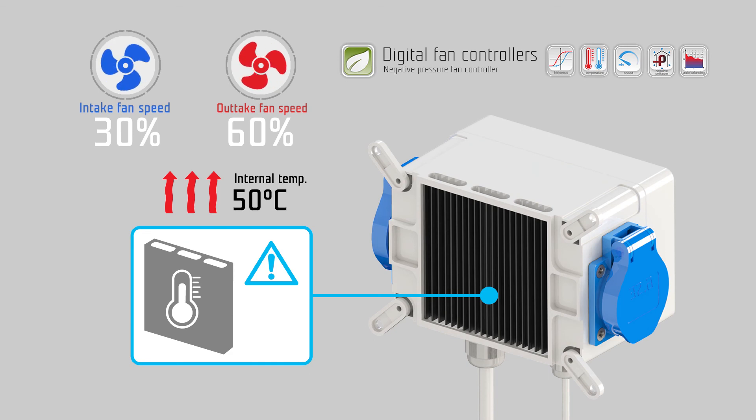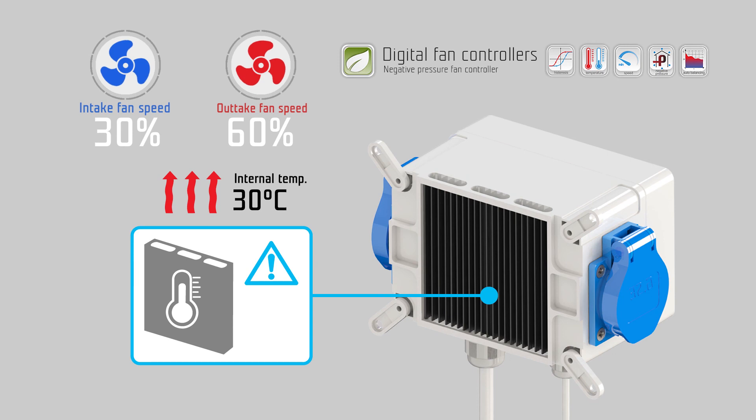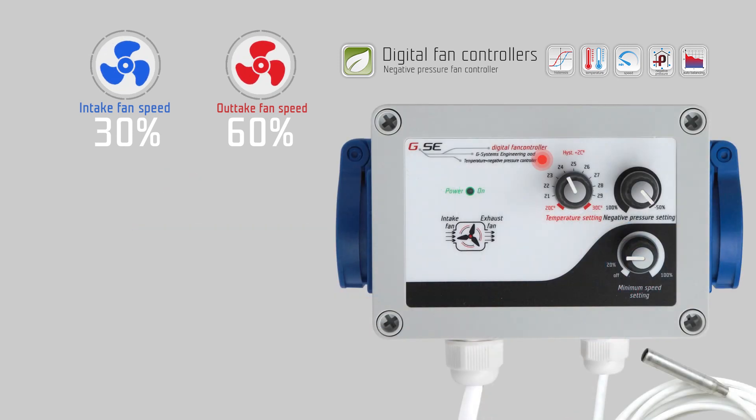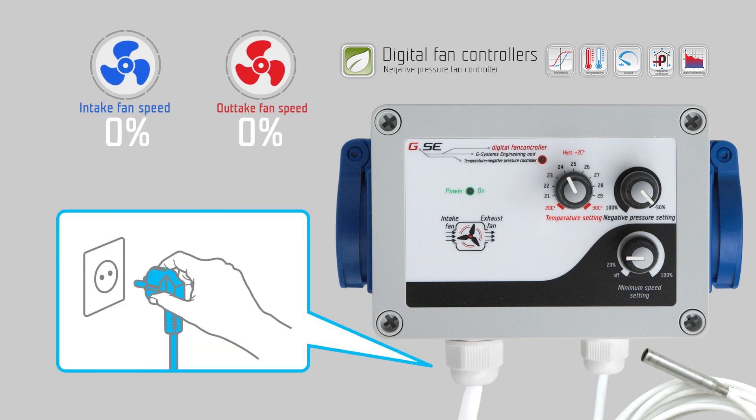The Negative Pressure Fan Controller has a built-in temperature surveillance sensor to protect from overheating. In case of overheating, the controlling range of the fans becomes fixed. While the controller is cooling down, the exhaust fan runs at maximum speed and the intake fan stops working. After the internal temperature falls below thirty degrees Celsius, the controlling range returns to variable fan speed, and the power LED indicates this with fast blinking.